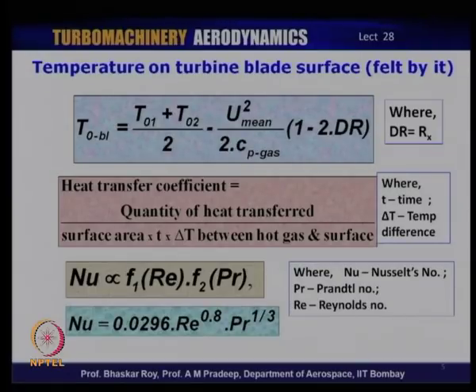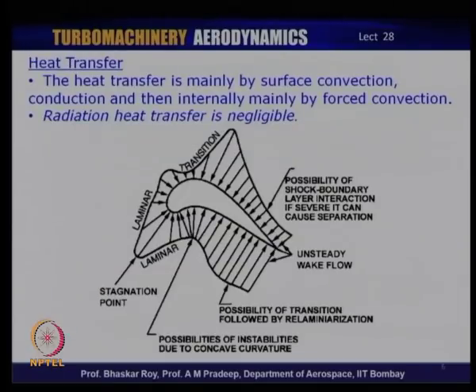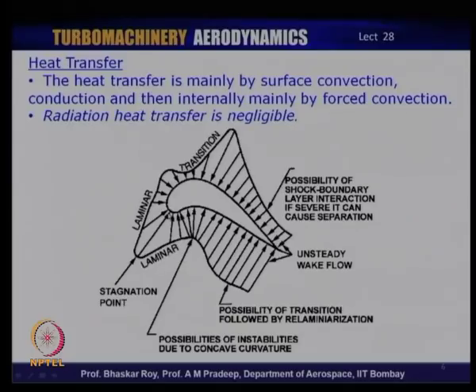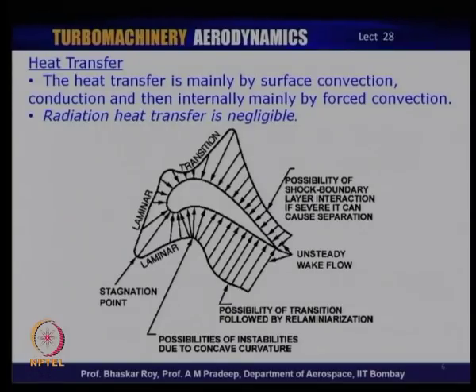This is the science and technology one needs for the turbine cooling business. When you have a blade, flow comes in at the leading edge, which is the stagnation point. At the stagnation point, the flow comes to a halt and thermally the total temperature equals the static temperature — meaning this point on the blade feels the entire total temperature of the gas flow, including the kinetic head. So the stagnation point is indeed the hottest spot on the blade surface.